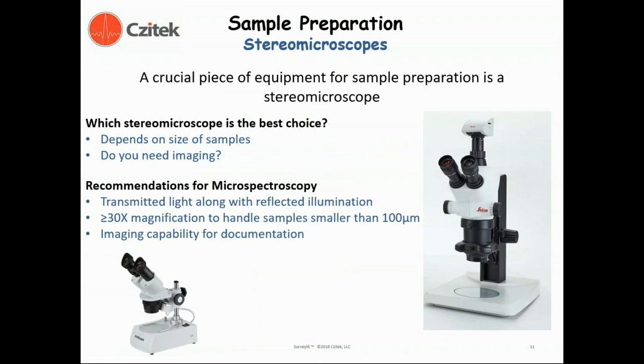A stereo microscope is indispensable. Stereo microscopes come in many shapes, sizes, and magnification capabilities. You can get one for a couple of hundred dollars that is perfectly adequate for most sample preparation. More sophisticated systems, like the Leica system shown on the right-hand side, cost several thousand dollars but have a much larger range of magnification, more working distance, flexibility, and a camera port to record images. We need greater than 30x magnification in our stereo microscope to handle samples smaller than 100 micrometers — that's an important thing to remember.